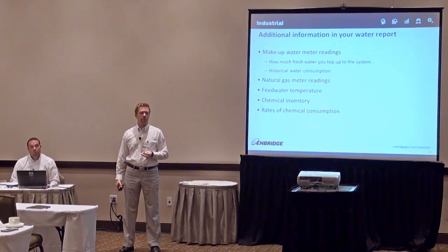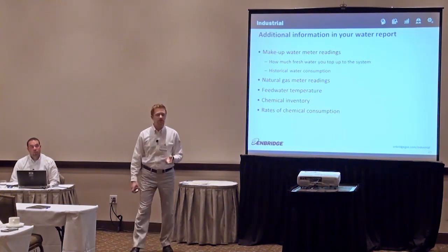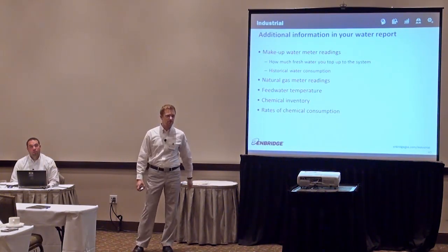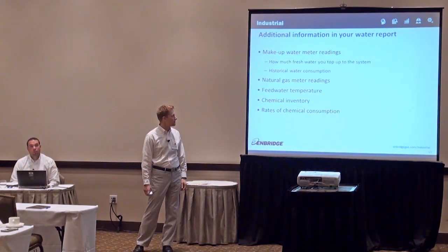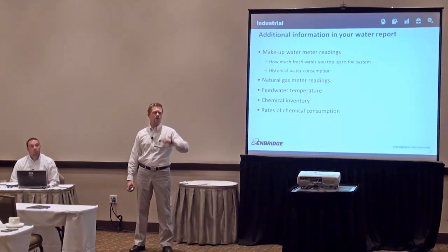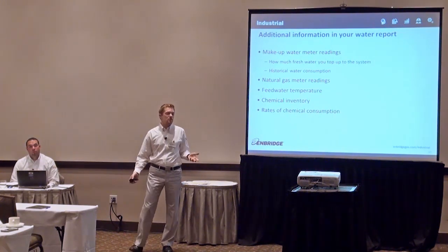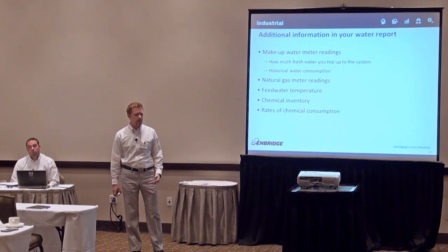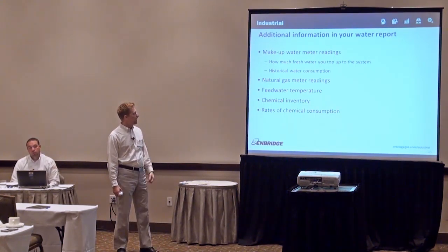You're also hopefully going to see historical water meter readings, maybe even a graph, depends on the report, which could be an indicator of lots of things. Maybe you've got a problem. Maybe there's condensate being lost because a GFI on the condensate receiver tripped or something like that, and now it's going to drain. I've seen all sorts of different versions of that. But if suddenly your water usage peaks, you know there's something going on there, and you can start investigating. Maybe it's process. Maybe you can say, oh yeah, we produced twice as many widgets last month. That makes perfect sense. Okay, so you're seeing the results of that in your water meter readings.